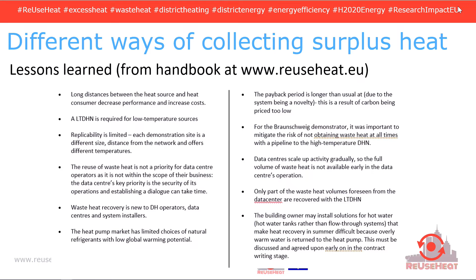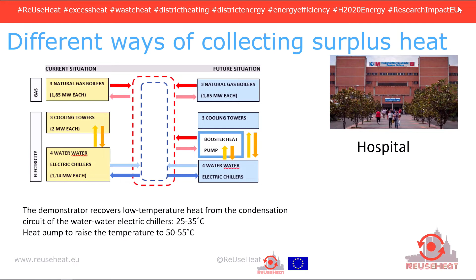Those were the learnings from that one. Then the hospital demonstrator, one of the largest hospitals in Madrid. This is its overall concept. We recover waste heat from the cooling towers, at about 25 to 35 degrees, and raise it with a heat pump to about 50-55 degrees. The big gain is that you can phase out the use of natural gas. This demonstrator has proven very successful, and it also added solar panels to run the booster heat pump on solar electricity, making it even more efficient than we foresaw.